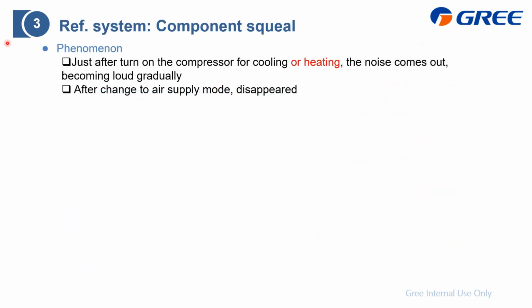Next, also a refrigerant system noise, but this time it is not the EXV, but other components. And the phenomenon is similar. First, it occurs no matter whether it is cooling mode or heating mode. Next, just after you turn on the compressor, the noise comes out and becomes loud or significant gradually, which means the refrigerant flow is making the noise. And the last is how to identify it: you can switch this indoor unit from cooling or heating to air supply mode, and if the noise disappears, then you can conclude it is refrigerant noise. And I will also play an example for your reference, just like this.